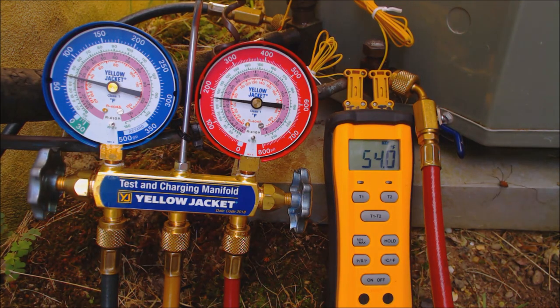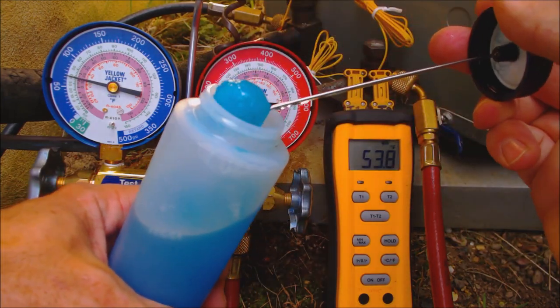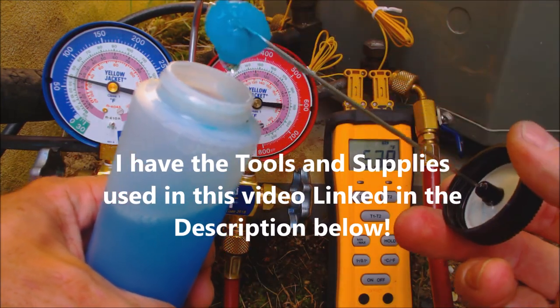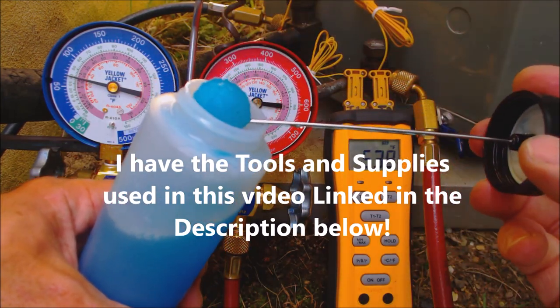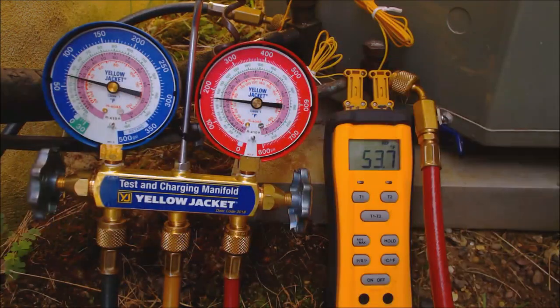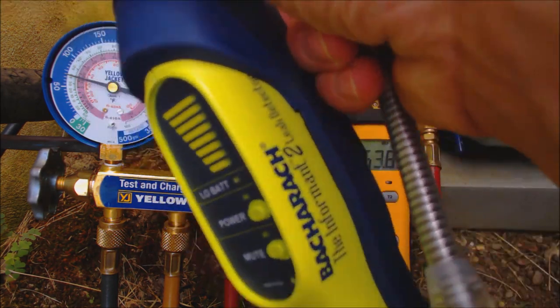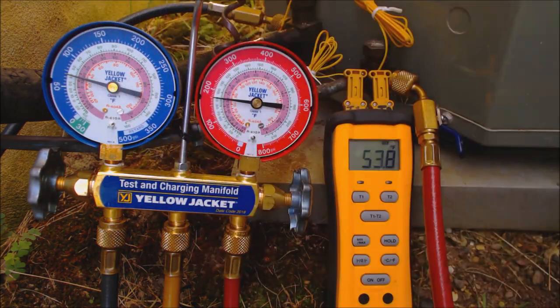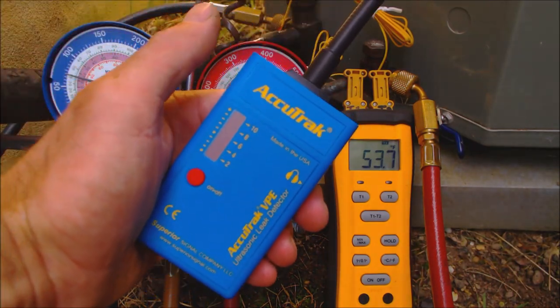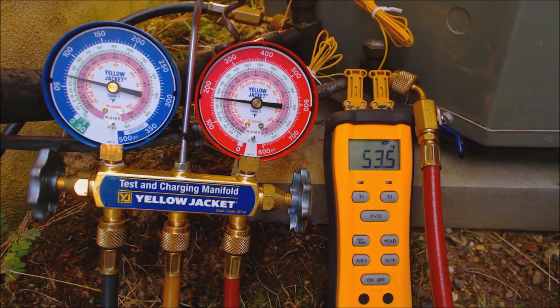If you are low on refrigerant, you can use a leak detector such as this bubble solution — rub it on all visible joints to find the leak. A lot of times the leak is in the coils of the outdoor or indoor unit, and you may need a more sophisticated tool such as an electronic refrigerant sniffer like the Bacharach Informant 2, an ultrasonic leak detector like the Accutrack VPE GN Pro, or another leak testing method.